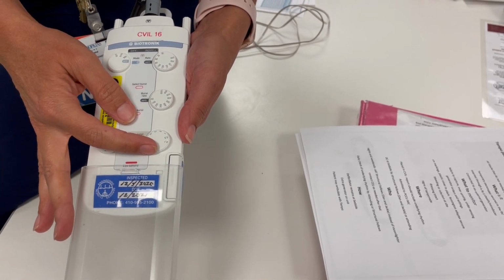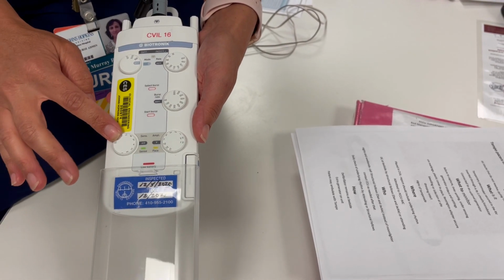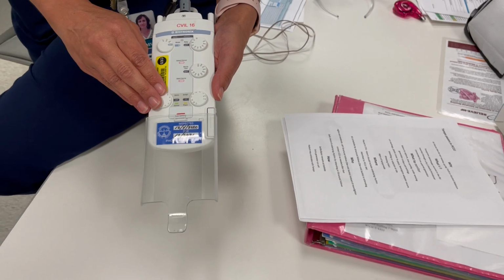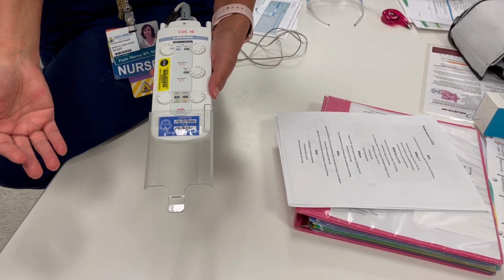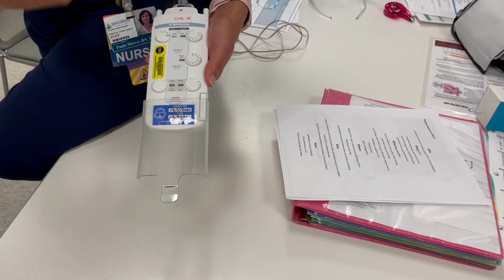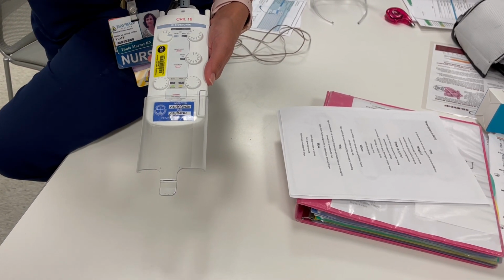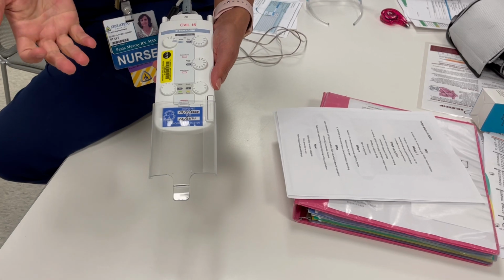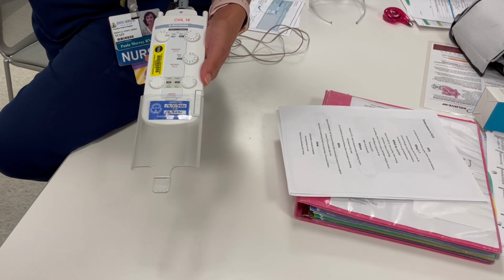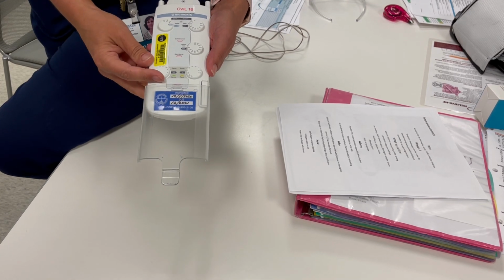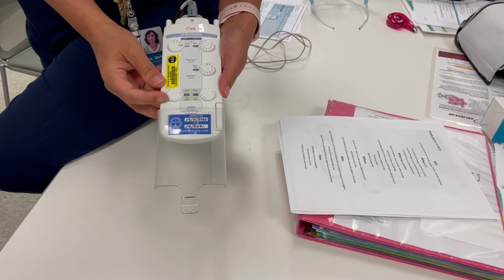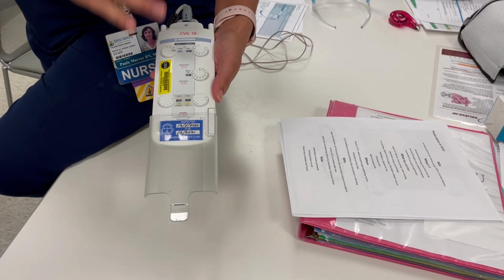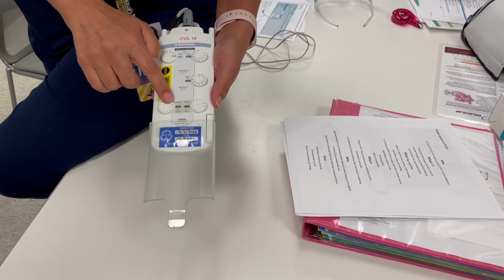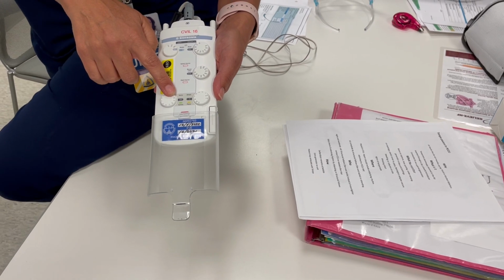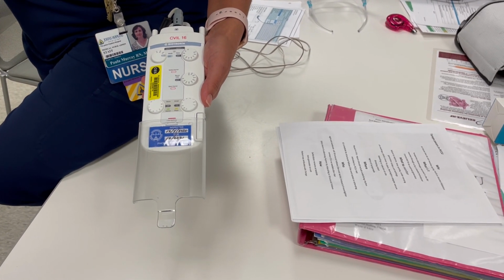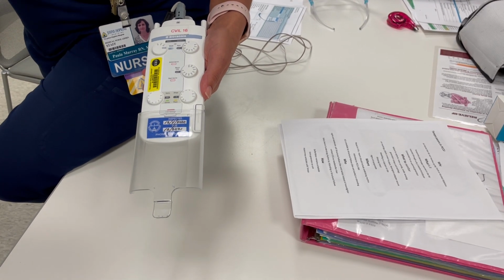The sensitivity tells you how sensitive the pacemaker is to the patient's intrinsic rhythm. This is going to be like a backup pacemaker, right? So we want it to inhibit when the patient has his own intrinsic rhythm. It doesn't make a whole lot of sense at first, and you will not be responsible for setting these. They will come already set. But a higher number means it's less sensitive to what the patient is doing, because basically it can't see what's happening.